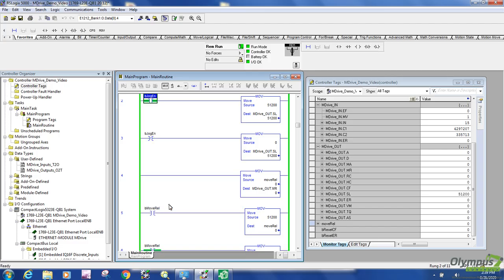All right, the motor should be jogging, which it is. You can see the position updating here. I'm going to go ahead and stop it by grabbing it with my fingers. And we should see error 107 and then error 104. Yes, there we go. So 107 is a locked rotor flag, and then 104 indicates a stall. All of the error parameters can be found in the M-code manual.